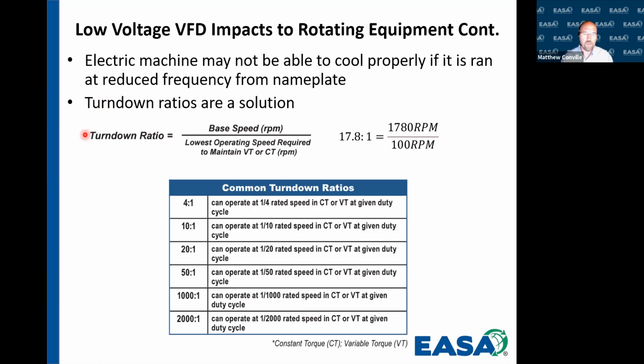And the turn down ratio, if we want to know what we need, we're going to take a look at what is the lowest operating RPM that we're going to be at on a regular basis, where we need to do work. And then we're also going to take a look at what is the rated speed, the base speed of the machine. So if you take the base speed of the machine and you divide it by the lowest operating speed that you need to do work, whether it be variable or constant torque, that's going to give you a ratio. So in our 4-pole example, if we needed to operate down to 100 RPM, and the nameplate was 1780, we're going to have a ratio of 17.8 to 1.